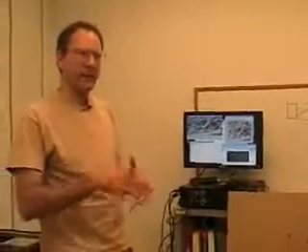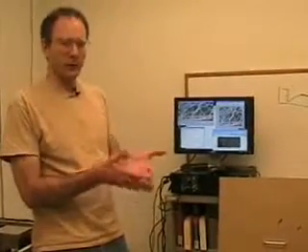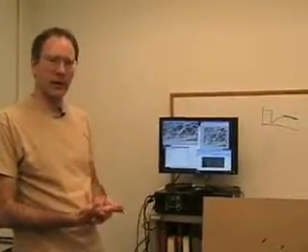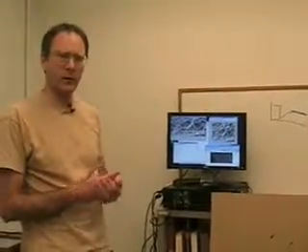It's a little out of focus, so I'm going to adjust my focus here. But as I move along the x-axis, and I'm going to move all the way to the edge here, now I've got my gain at 512, which is its maximum. The shutter is its maximum, and I've got a certain amount of saturation. The thing that's important here is you want to increase your light first, then your shutter time, and after that your gain. The reason for that is that by increasing the light, you increase the number of signal photons you get, which is what you want to do. You want to see an image from signal.